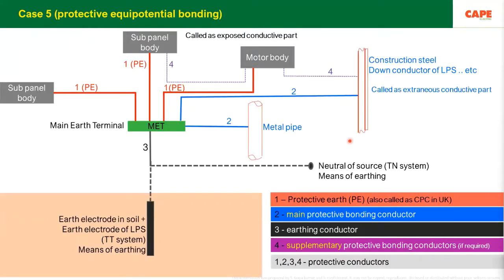Now, case number 5, protective equipotential bonding. What it means is, in every building, all the metallic parts, except current carrying conductors or some communication wires, must be interconnected in such a way that there is no shock hazard. There are rules on how to connect and where to connect. Primary protection, supplementary protection, protective bonding, protective earthing, different words are there. But basically, for a non-engineer to understand, very simple: every metallic part in your building must be electrically interconnected, except the phase and neutral conductor, to avoid shock.